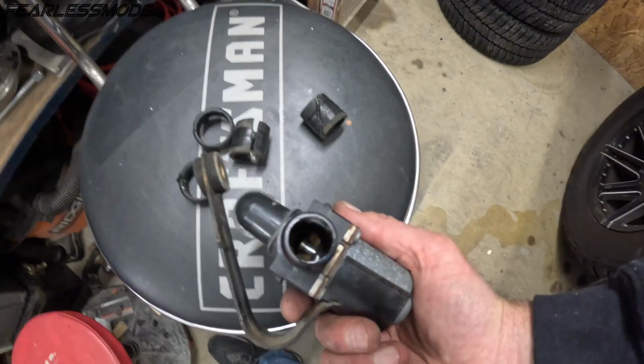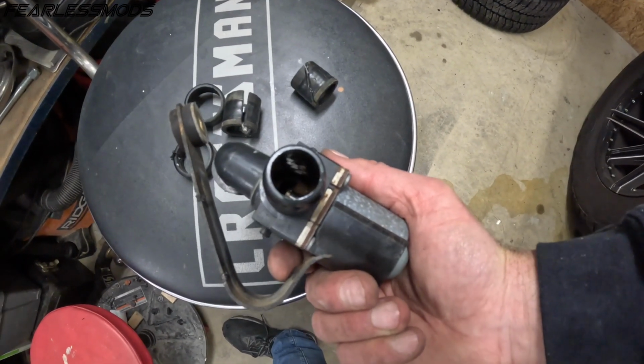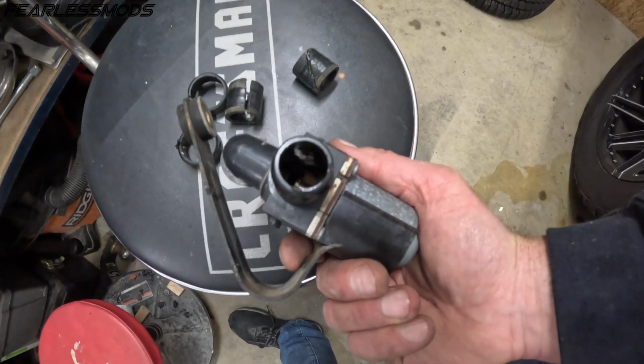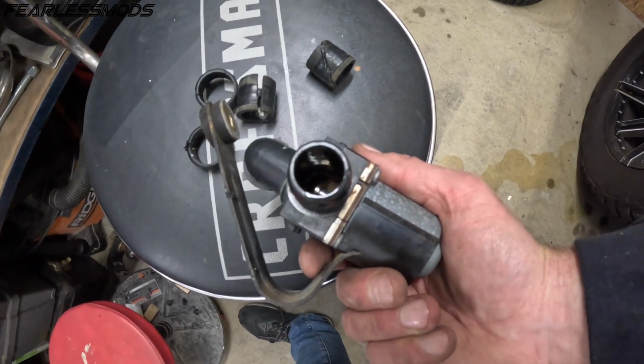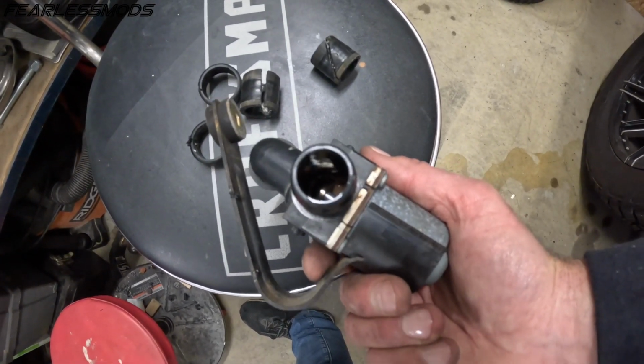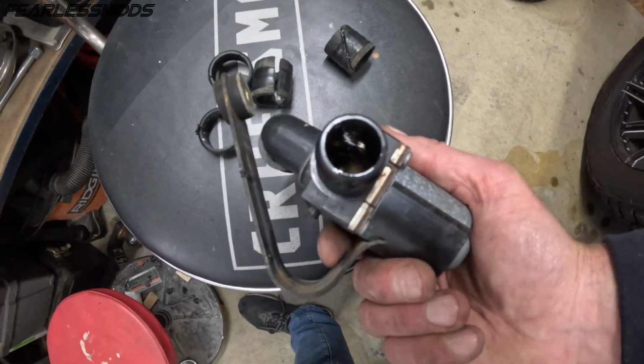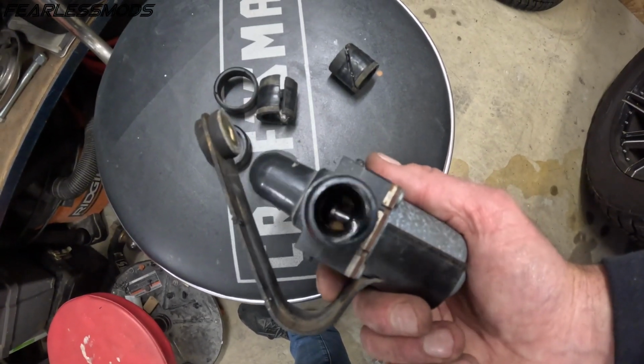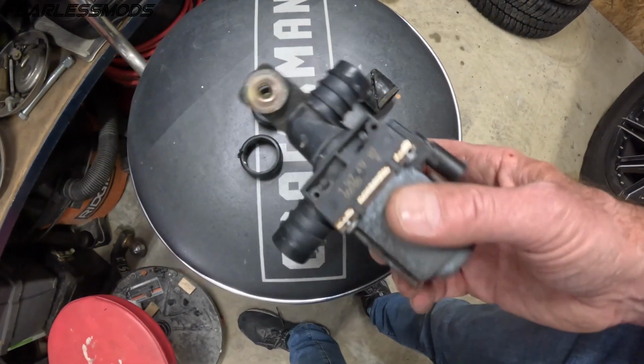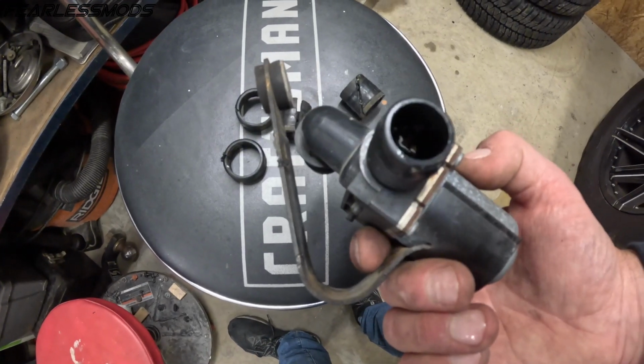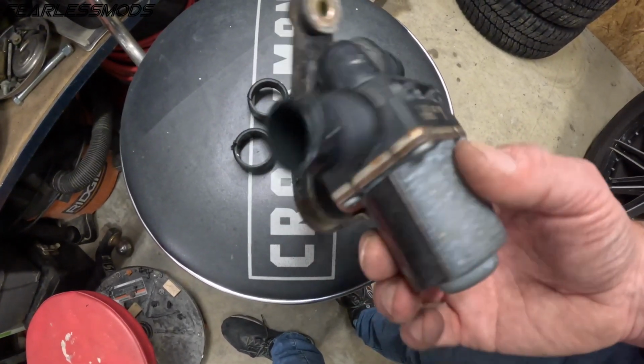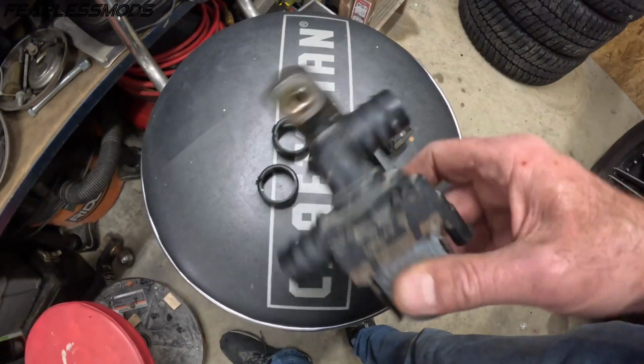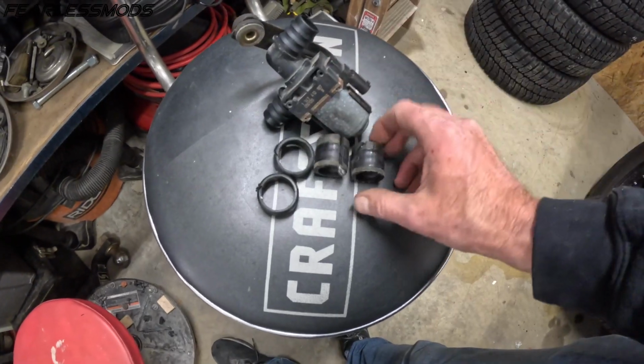Double check that with that valve open like it is automatically, I can blow through it. And then I stuck a screwdriver in there, just underneath the plunger head, pulled it up into the closed position, and I can't blow through it. So we know that it works electrically, and we know that it is sealing the flow when it's closed, and it's flowing when it's open. So this thing's working like a champ, amazingly enough.